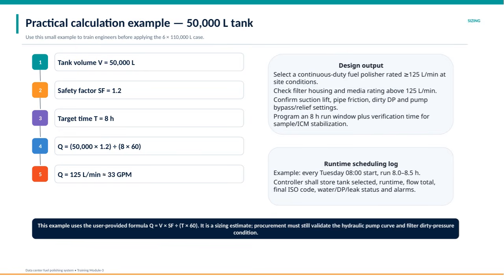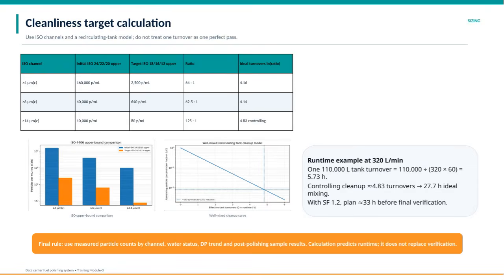Remember, this example uses the formula Q equals volume times safety factor divided by runtime in minutes. While this provides a good sizing estimate, final procurement decisions must validate the hydraulic pump curve and account for filter dirty pressure conditions to ensure reliable operation. Here we focus on how to calculate cleanliness targets using ISO channels and a recirculating tank model. It's important to note that we don't consider one turnover as a perfect pass. This realistic approach ensures more accurate sizing and runtime predictions.